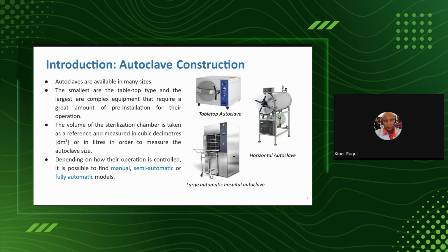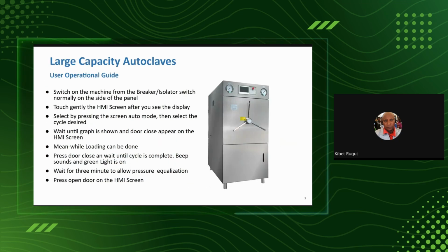Most of them, again, are sliding door because of their huge capacity in cubic meters. An autoclave like this we consider large capacity because it can sterilize goods that can service maybe even 3 or 4 operating rooms. In terms of operation, it has power isolation switches. It has a programmable interface, an HMI screen, which shows you a display. When this display comes on, you can select either automatic or manual mode and pick up the preset cycles. Once you do that, sometimes the interface provides for you to intervene in a program if there is a problem or if you want a change for some reason. Again, there is a printer or a graphical display that monitors the temperatures and also monitors whether doors are opening or closing.